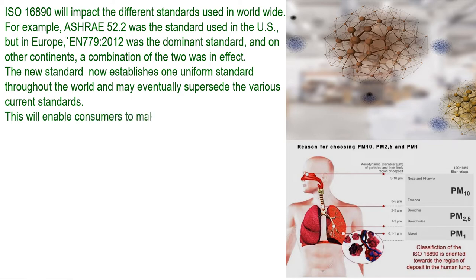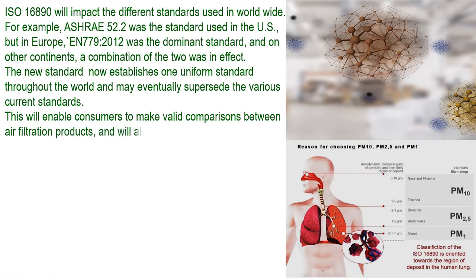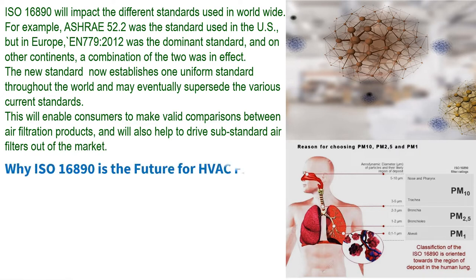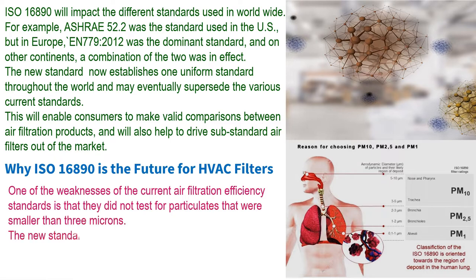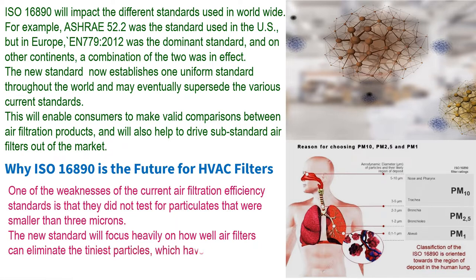This will enable consumers to make valid comparisons between air filtration products and will also help to drive substandard air filters out of the market. Why is ISO 16890 the future for HVAC filters? One of the weaknesses of the current air filtration efficiency standards is that they did not test for particulates smaller than 3 microns. The new standard will focus heavily on how well air filters can eliminate the tiniest particles, which have been identified as the most hazardous to human health.